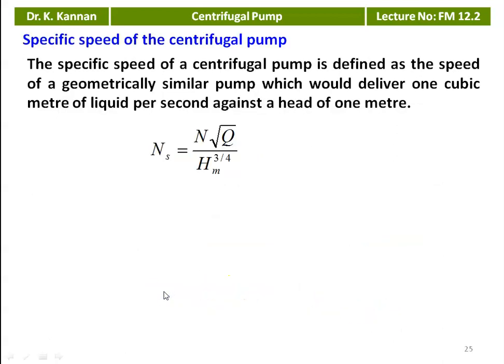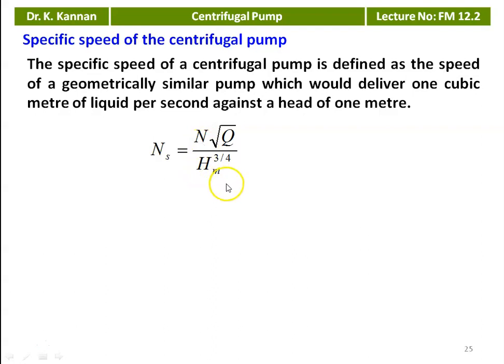The specific speed of the centrifugal pump is defined as the speed of a geometrically similar pump which would deliver 1 cubic meter of liquid per second against a head of 1 meter. The formula is Ns = N·√Q / Hm^(3/4), where Q is the discharge, N is the speed, and Hm is the manometric head. Specific speed is an important parameter for the design of centrifugal pumps and is used to compare the performance of different types of pumps of similar capacity.